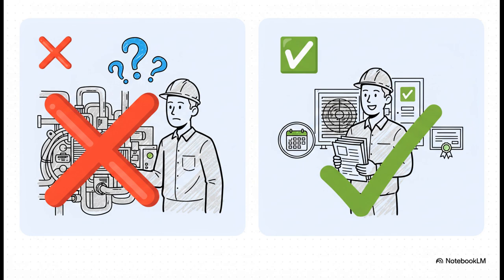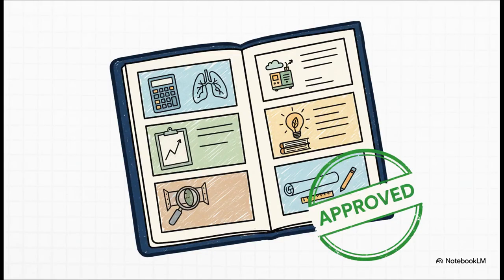No plan, no handover. And so, this is it. This is the master checklist. This is your passport to getting paid. You need the final calculations for fresh air and cooling load, the duct leakage test results, the final TAB report. For special cases, you need those hospital pressure tests and VRF gas reports. And to wrap it all up, the energy model, the complete O&M plan, and of course, the final as-built drawings. Have this binder ready to go, and you are in total control.